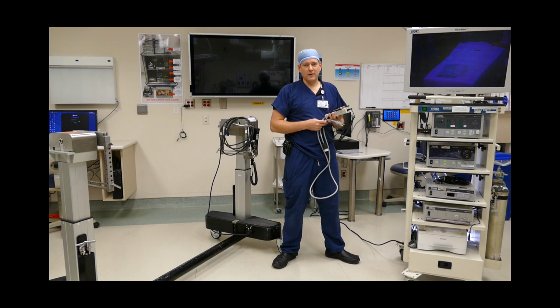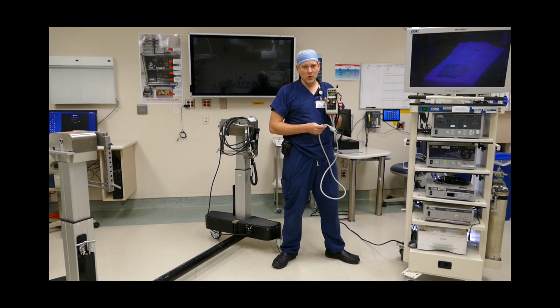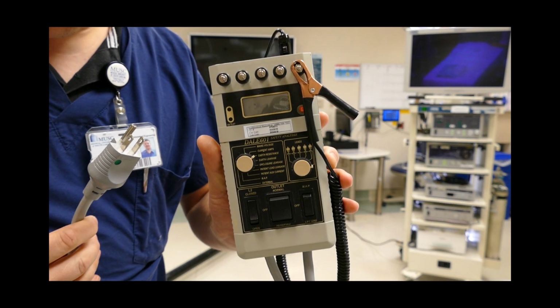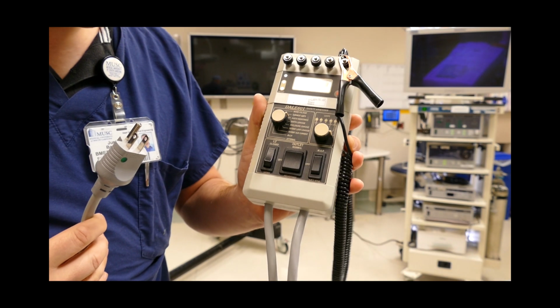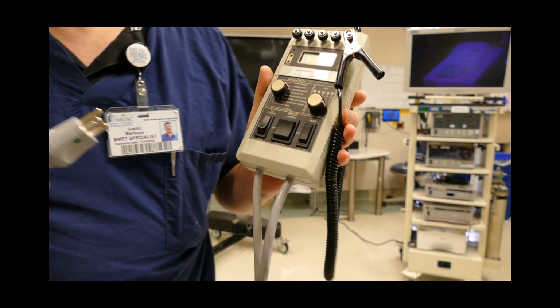Portable devices are allowed 500 microamps of leakage with the grounds lifted and 100 microamps of leakage when the ground's intact. So today I'm going to be using a Dale 601 meter. This is a pretty standard electrical safety meter. Allow you guys to see it up close. Pretty simple, just a couple dials, some flip switches.